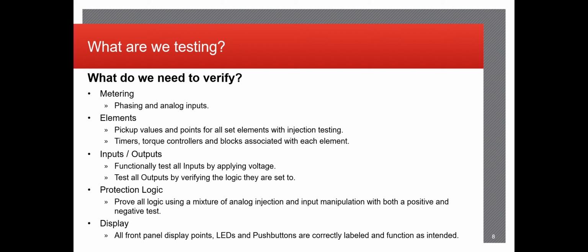The positive and negative tests pretty much mean that, depending on the scheme, you want to make sure that the relay only operates for what you're trying to look for. If it operates on a trip output one way and then you test it to make sure it doesn't do it the other way, and it ends up operating, then you know it's a failed test and something needs to be looked at, whether it's in the relay logic itself or even in the circuits. As well, you're looking at the display, all the LEDs, and push buttons, making sure that those line up correctly with what the client's looking for.